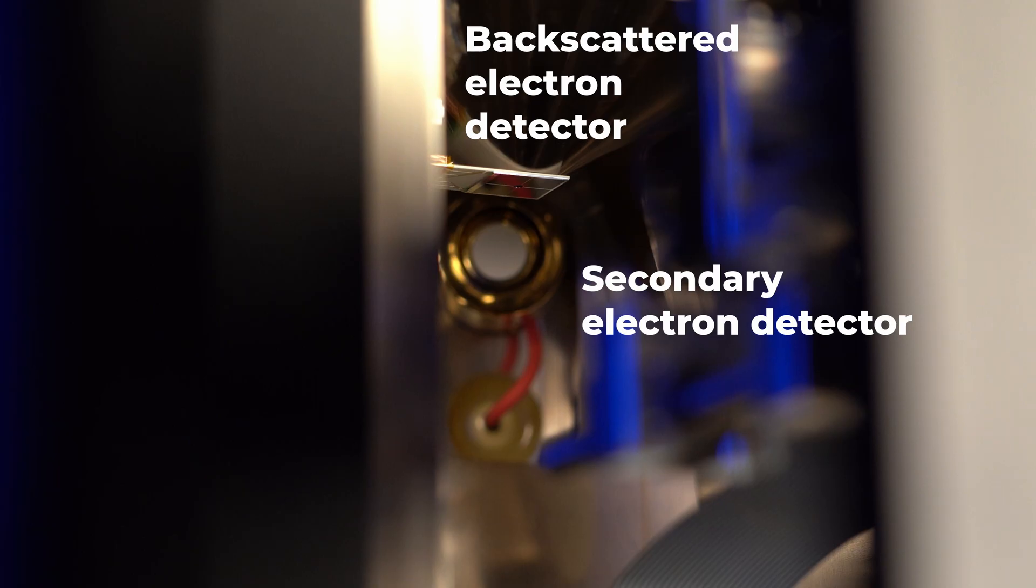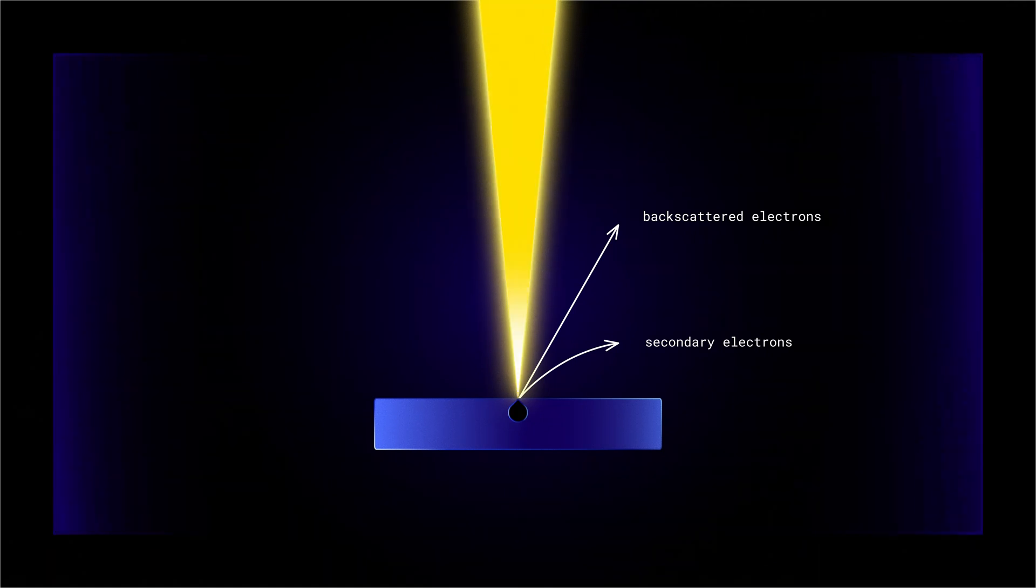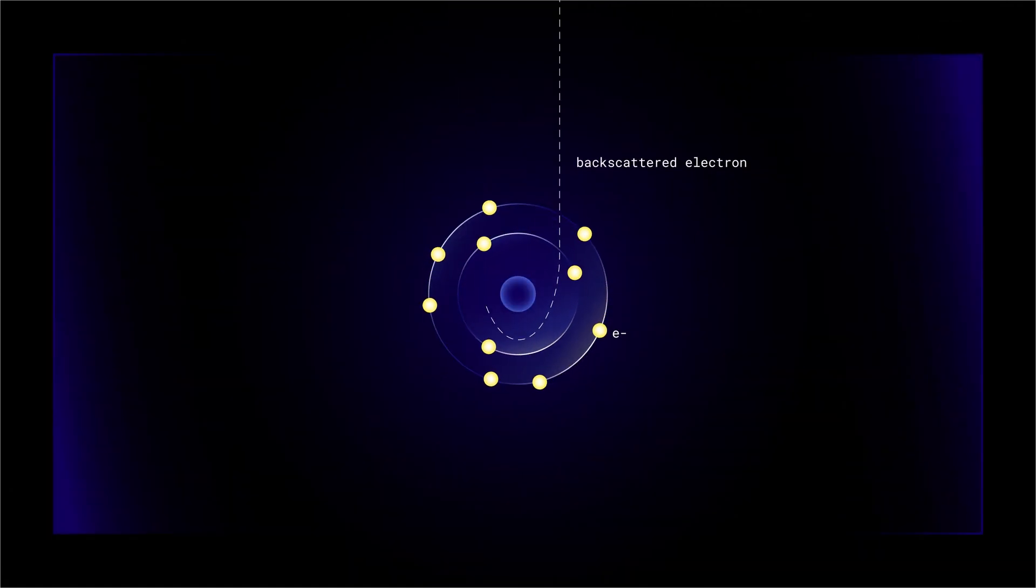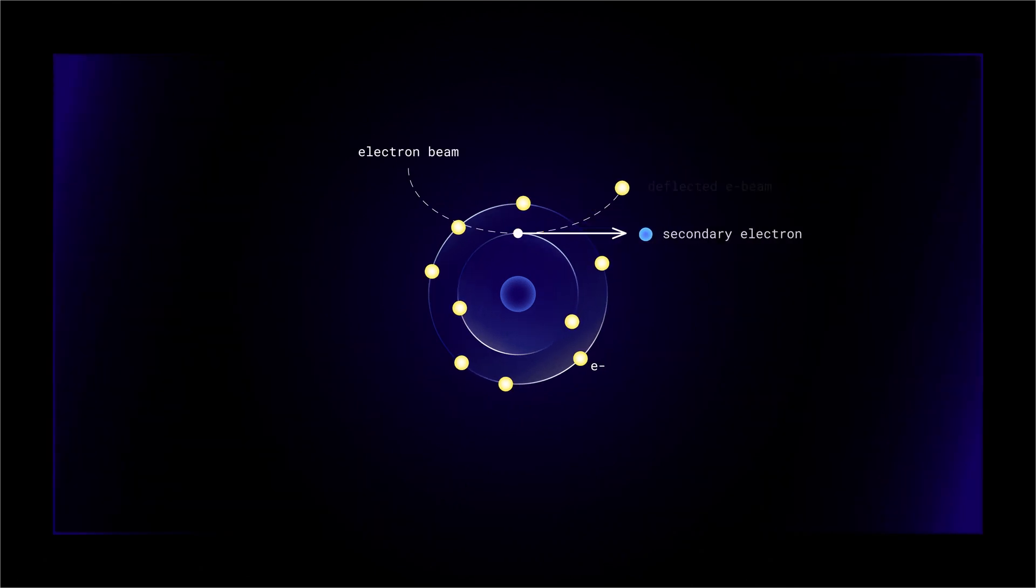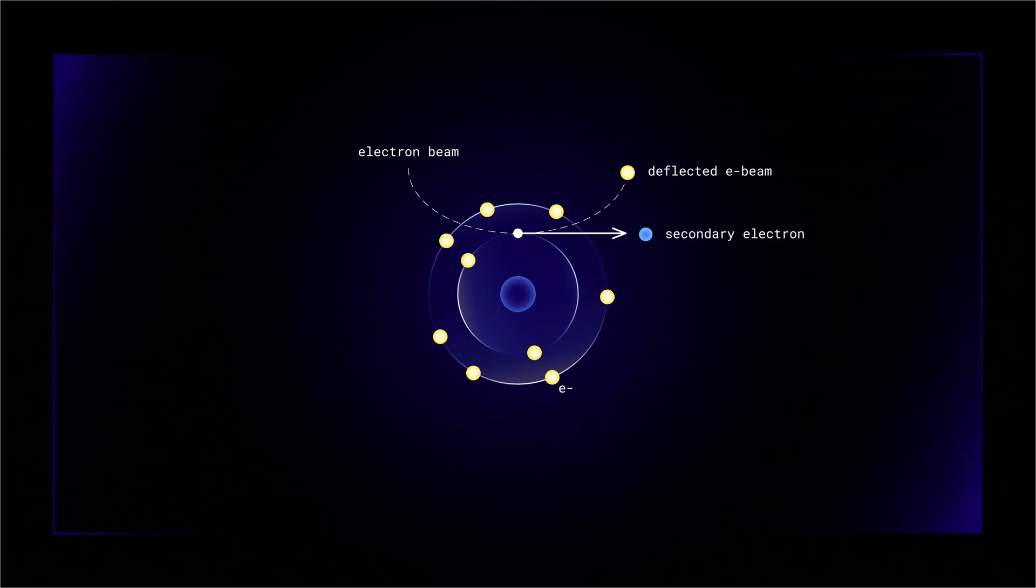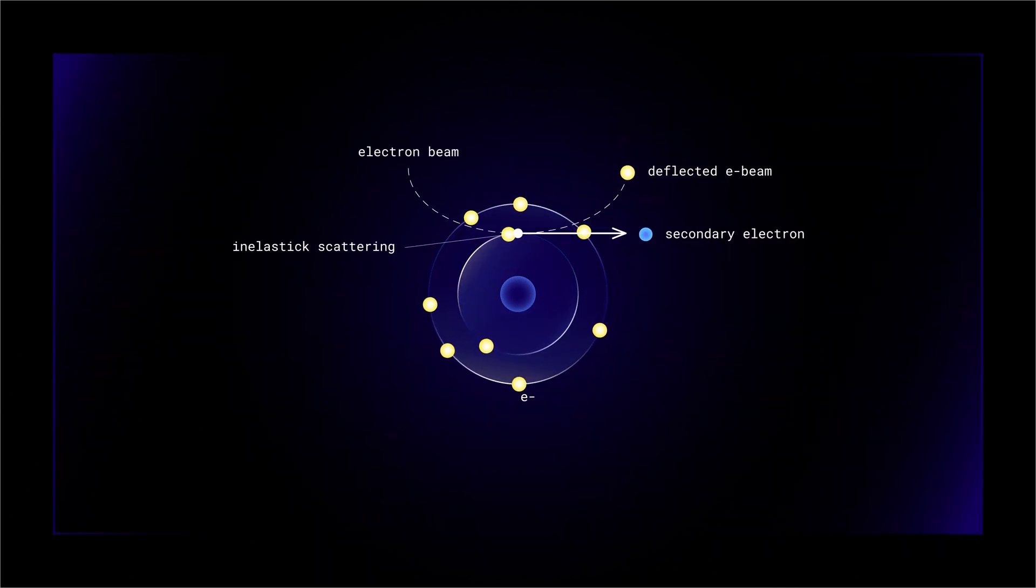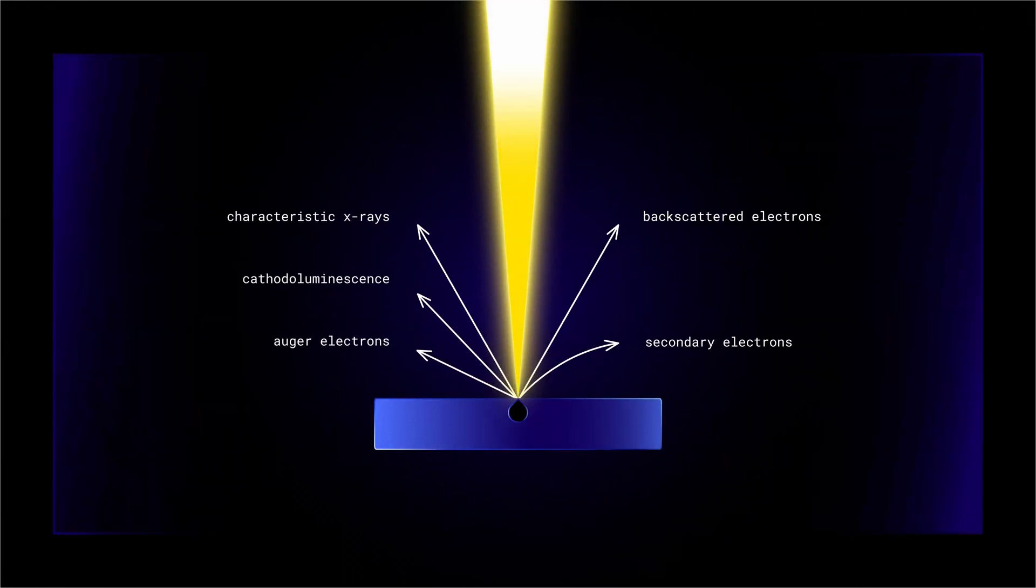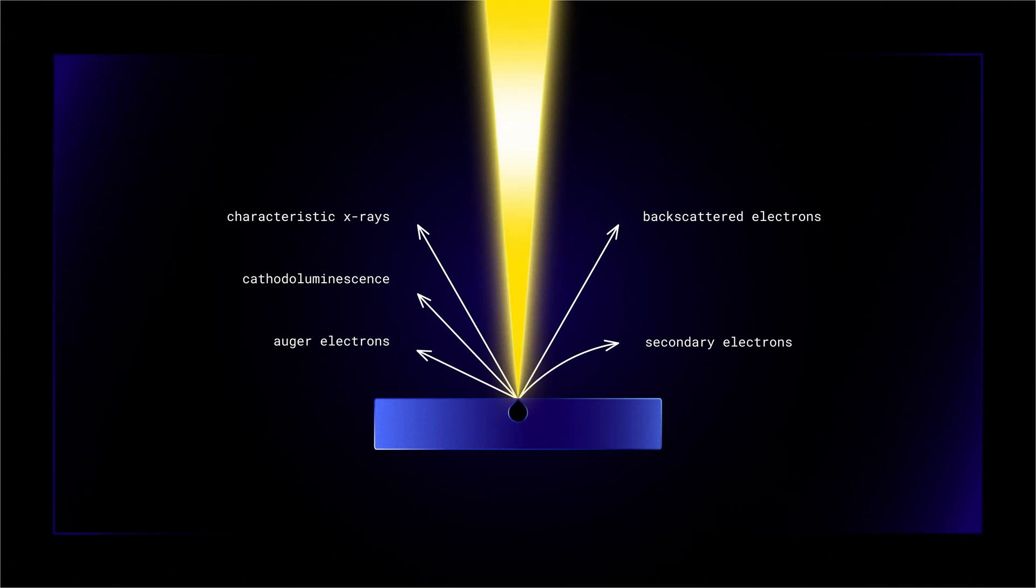In our case we have two detectors – secondary electron detector and backscattered electron detector. When the electron beam hits the sample it interacts with the atoms in that sample. There are a number of outcomes. Some electrons bounce back out of the sample called backscattered electrons. Others knock into atoms and displace electrons which in turn come out of the sample called secondary electrons. Alternatively, x-rays and light or heat in the sample can be the result of these interactions.